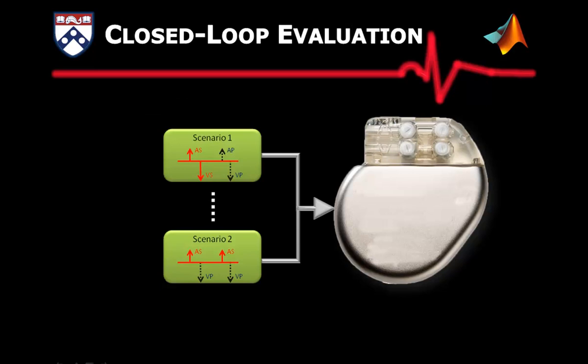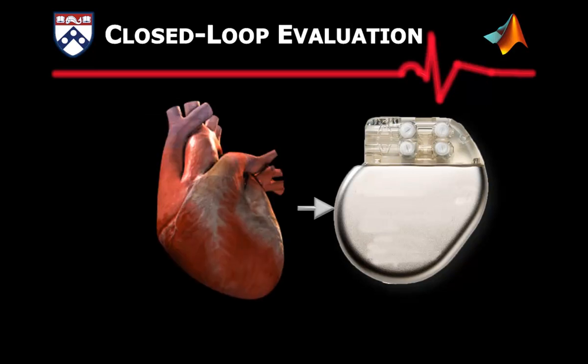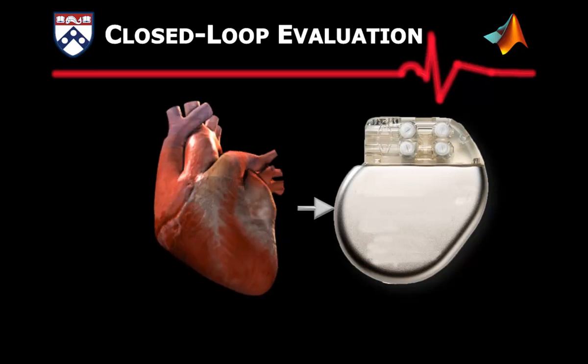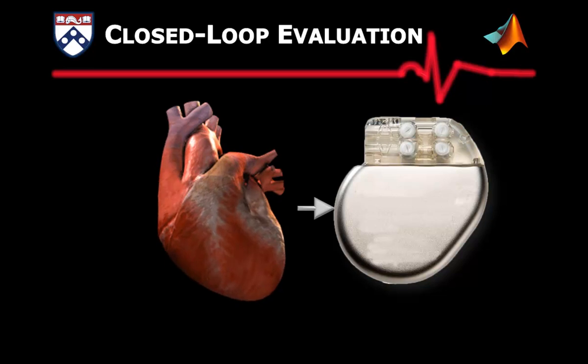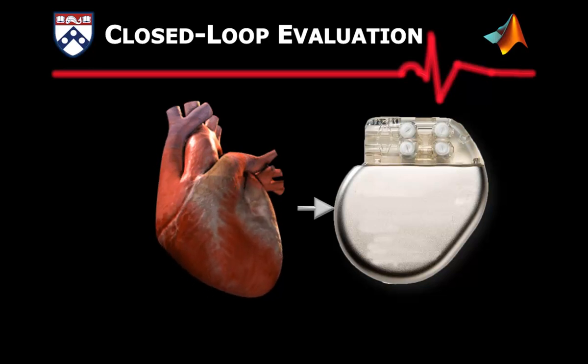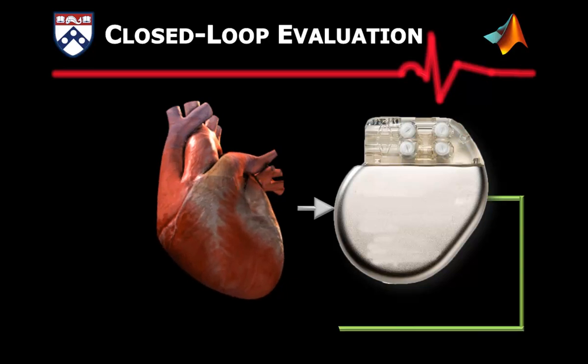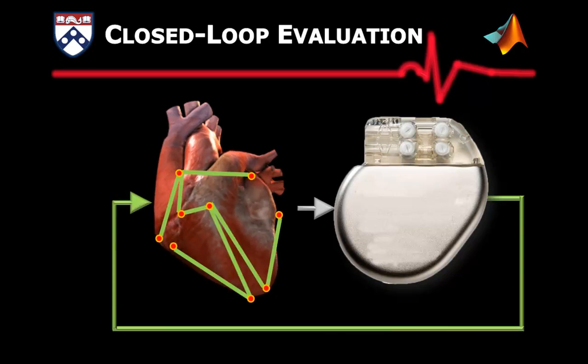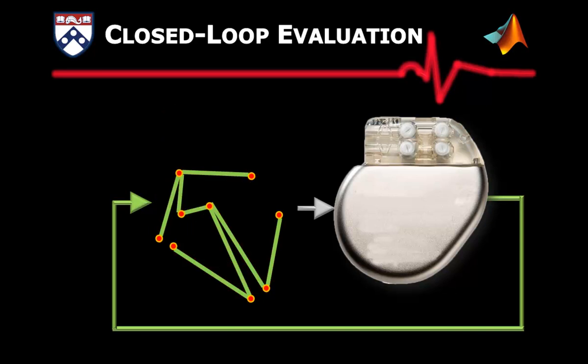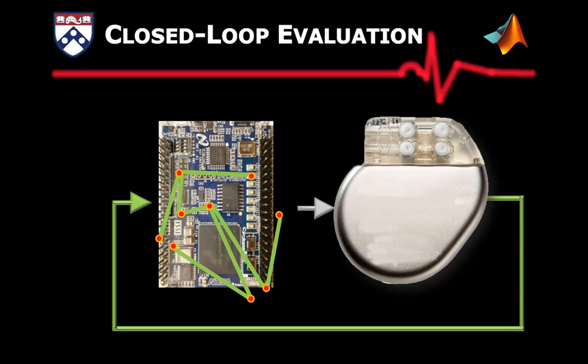The heart and the pacemaker form a closed-loop system where the output of the pacemaker changes the state of the heart. So instead of using recorded test cases to represent different heart conditions, we developed a heart model which simulates the electrical behavior of the heart and responds to pacemaker outputs. The model is also implemented on hardware to test the pacemaker in closed-loop.